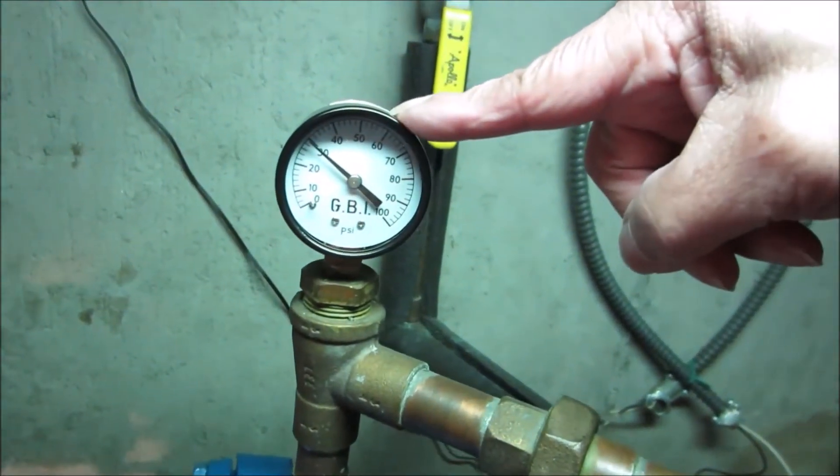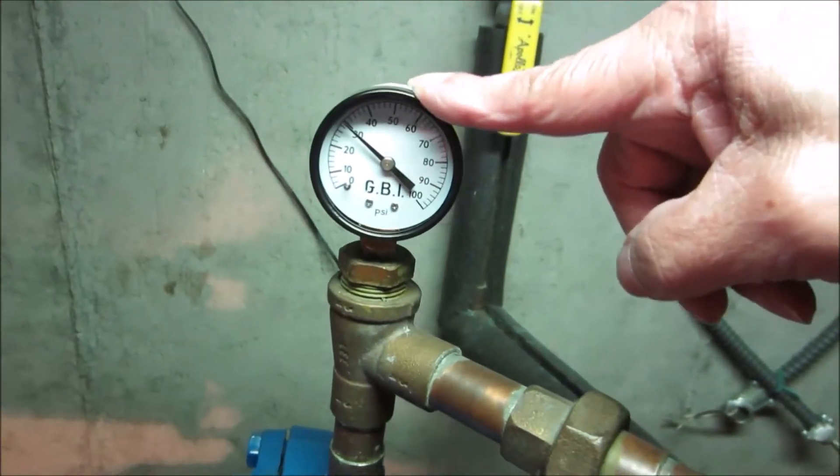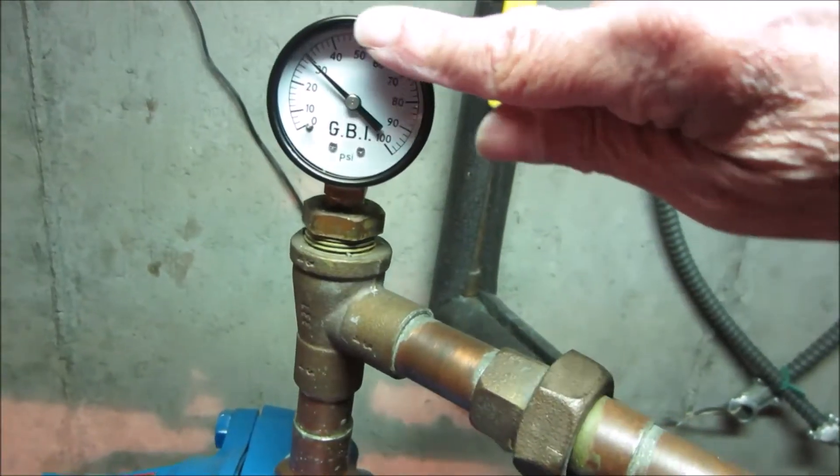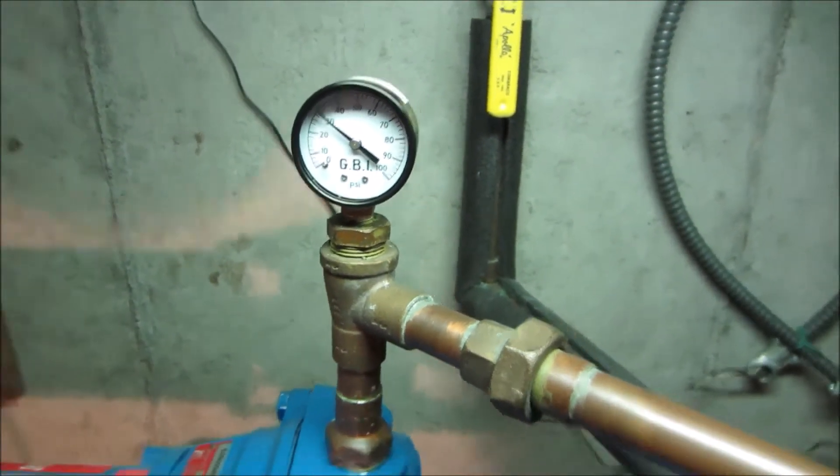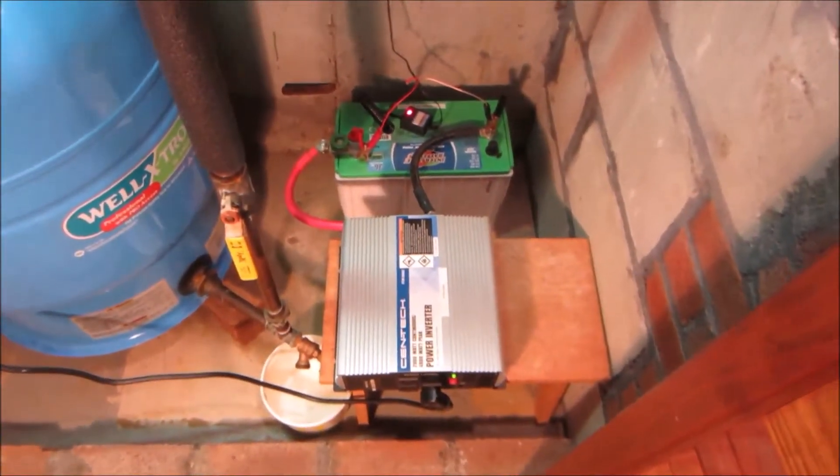When the pressure gauge calls for water — and it will be calling real soon because this is a 30-50 switch, so we're right about the cut-in pressure — it will draw power from the system and start pumping.